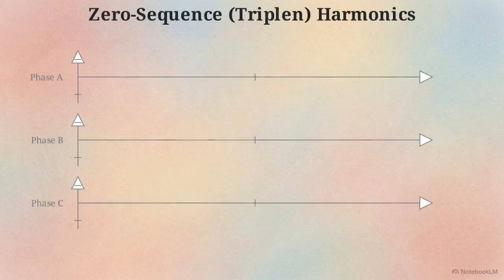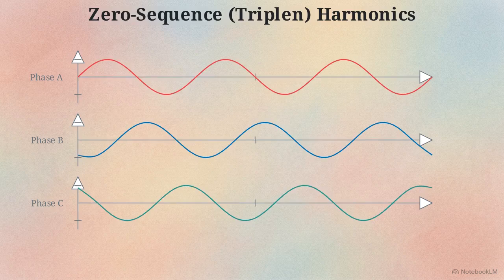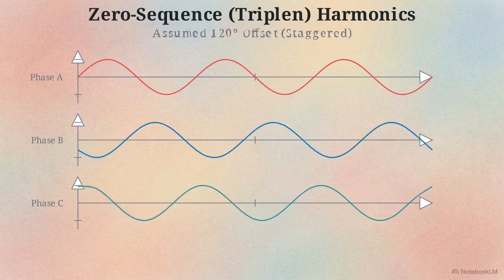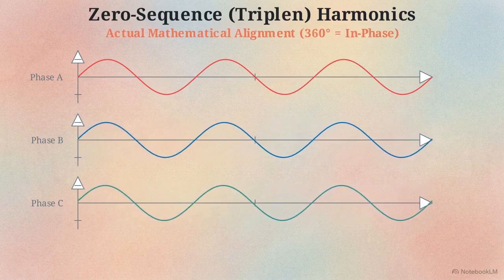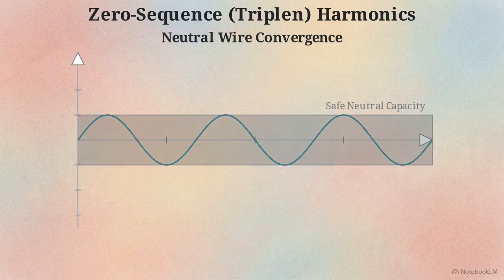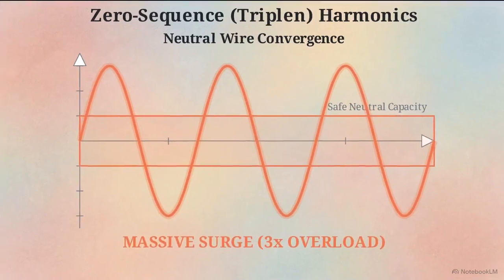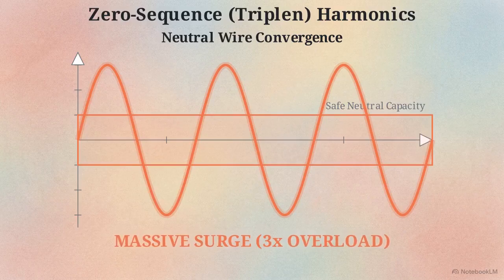This diagram shows the math behind the problem. Because triplens are exact odd multiples of 3, that standard 120-degree offset we saw earlier doesn't separate them. Instead, it perfectly aligns their peaks and valleys. When these specific frequencies hit the neutral wire, they arrive at the exact same time, completely in phase. Instead of canceling out to zero, they stack. They combine cumulatively into a massive, aggressive surge of energy.